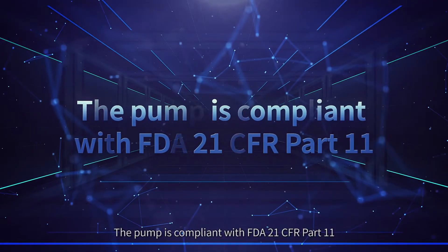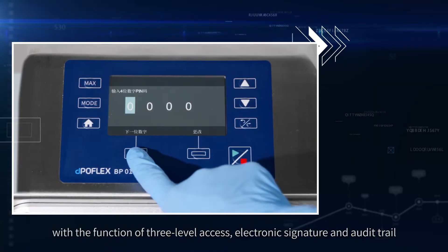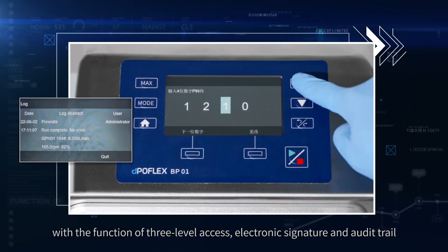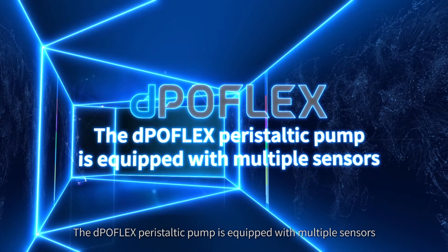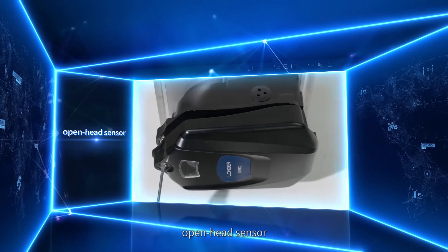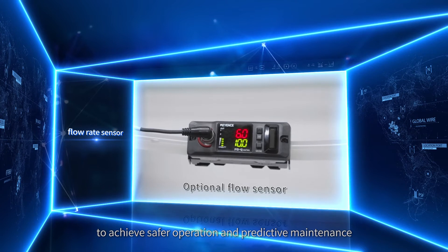The pump is compliant with FDA 21 CFR Part 11, featuring three-level access control, electronic signature, and audit trail. The dPOFLEX peristaltic pump is equipped with multiple sensors — a fluid leakage sensor, open head sensor, and flow rate sensor — to achieve safer operation and predictive maintenance.